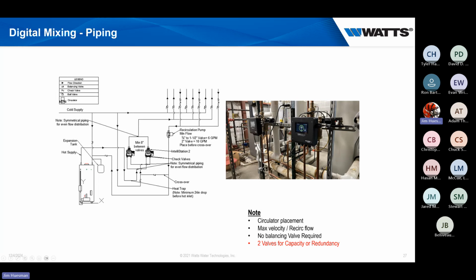So doing more of a dual system - trust me, when you look at the pricing of one 2-inch valve versus two 1-inch valves, you'll find it's pretty close. We might be slightly over by adding two valves, but it's definitely not doubling the price of the entire system. It gives us the ability to actually work off both valves at the same time. If there are problems, don't worry, we've got redundancy, we're good.